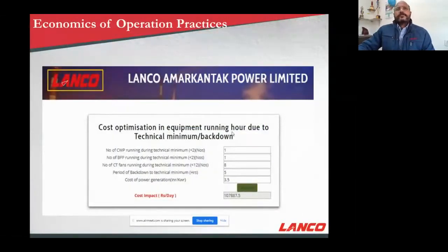So coming to cost optimization in equipment running due to the technical minimum of back down, I said that nowadays we are getting back down. So different plants have different strategies. If we can capture all those strategies, we can always evaluate our performance: are we availing all the options available with us judiciously in reducing our expenditures when we are running at the minimum load? Like running a reduced number of CW pumps, number of BFPs, cooling tower. Some plants go for ID fan shutdowns or PA fan shutdowns. So those combinations have been put here, and their impact on the cost is calculated.